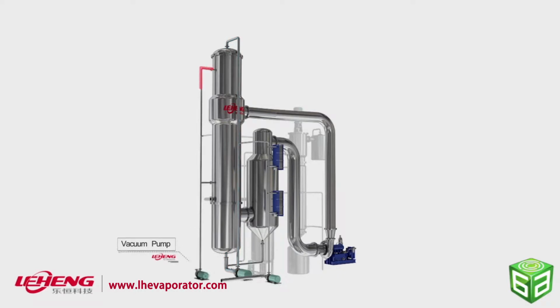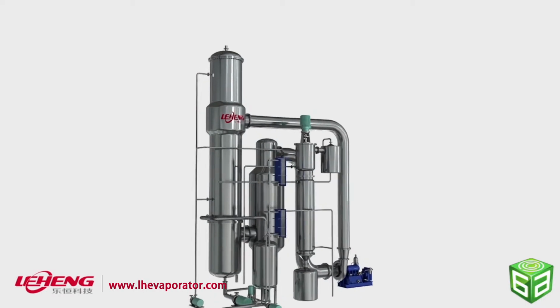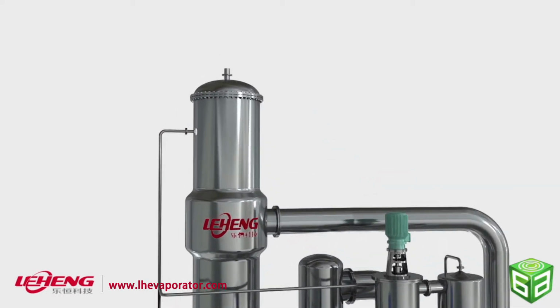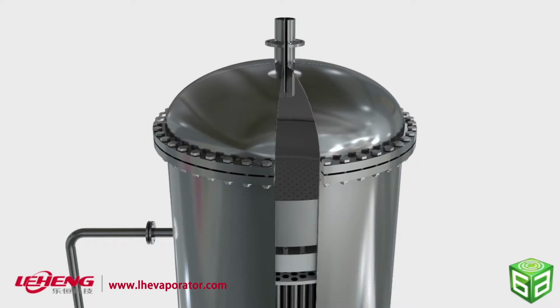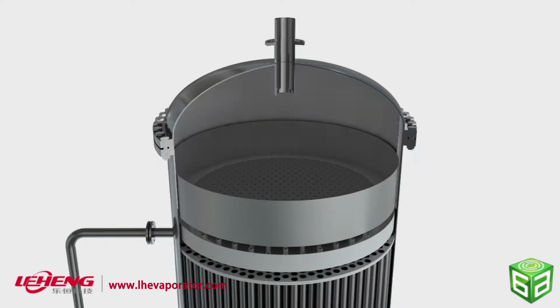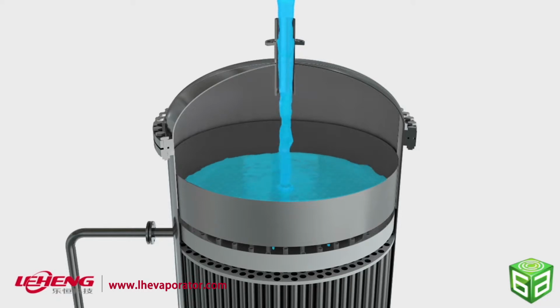The extraction of the non-condensable gas will be completed through a vacuum pump, which helps to maintain a stable vacuum level in the system. Feed liquid is introduced at the top of the falling film evaporator and spreads evenly through a distribution plate.